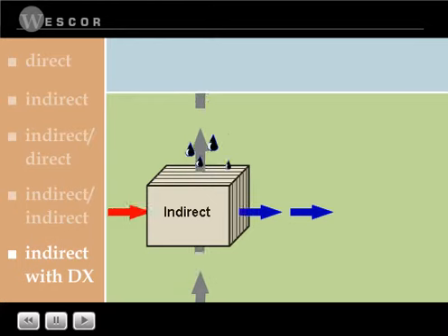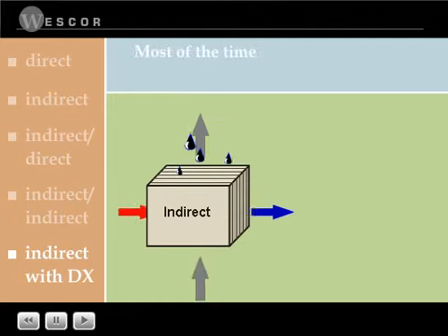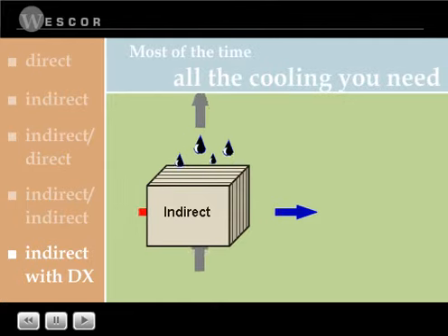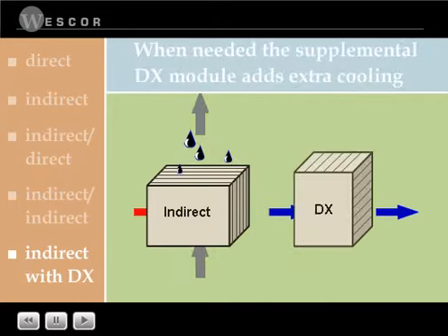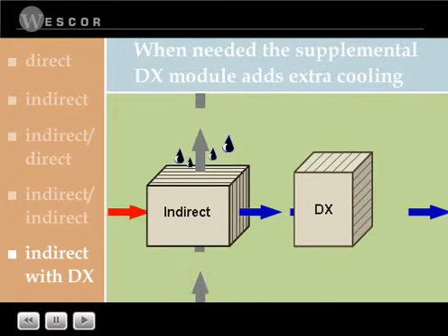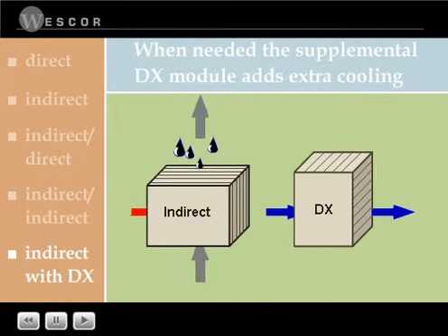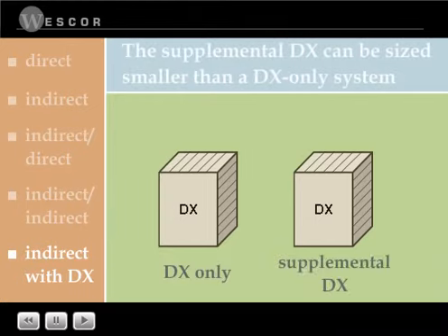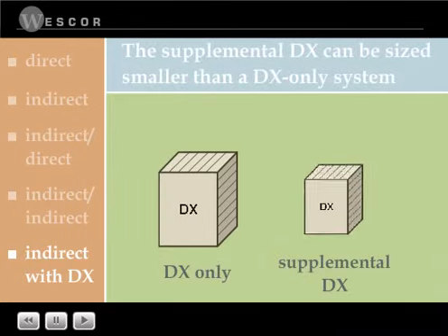With indirect evaporative cooling with DX backup, the primary airstream is cooled with indirect evaporative cooling. Most of the time, this cools the primary airstream to the desired temperature. But when more cooling is required, the supplemental DX module further cools the air until it reaches the desired temperature. The supplemental DX can be sized to a fraction of what a DX-only system must be sized at.